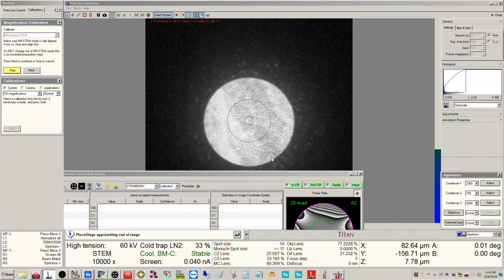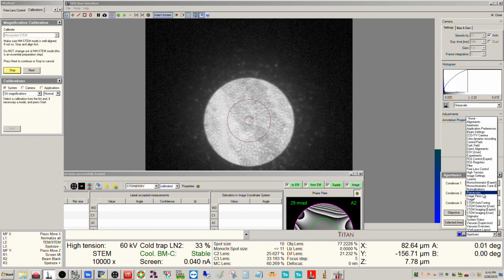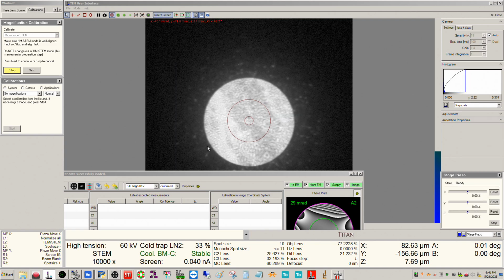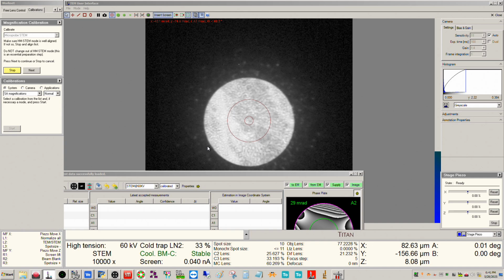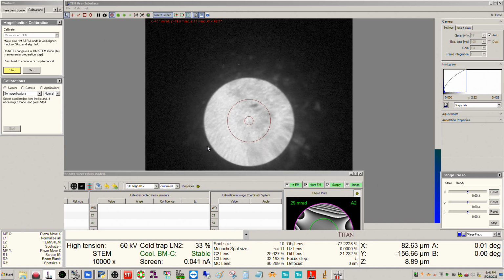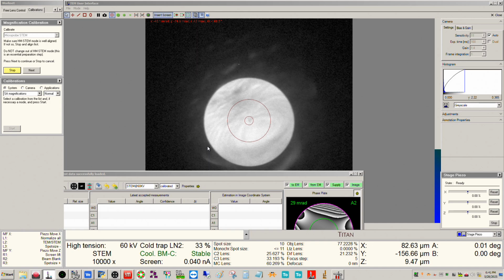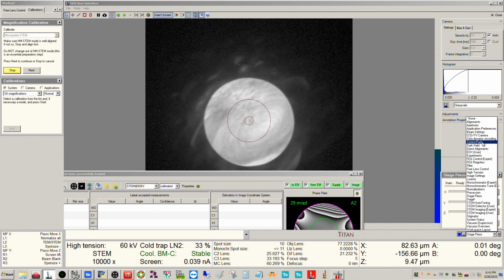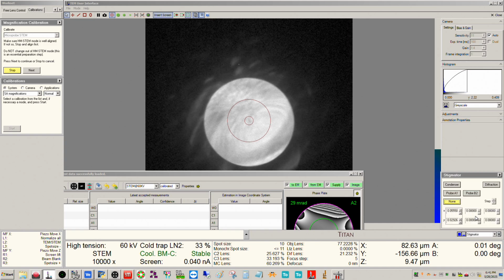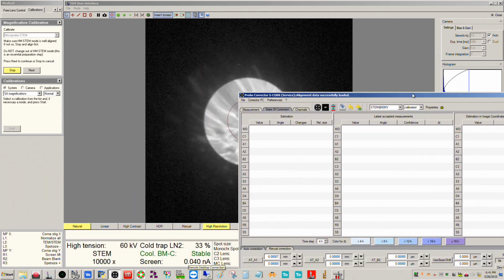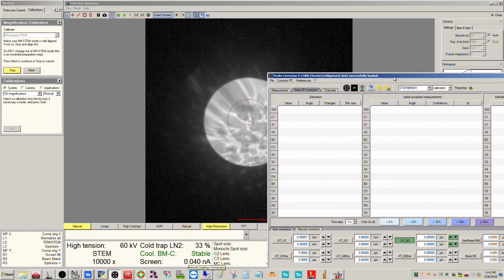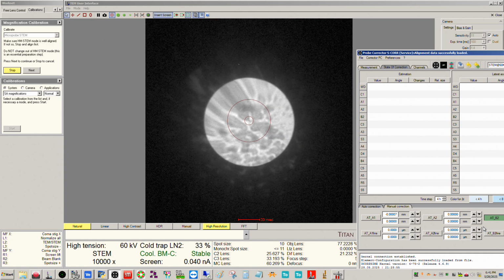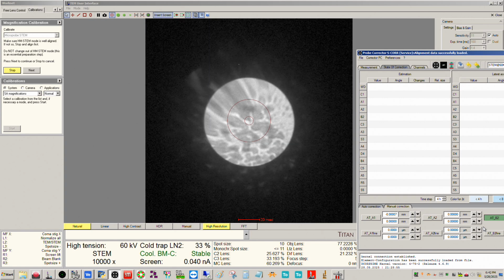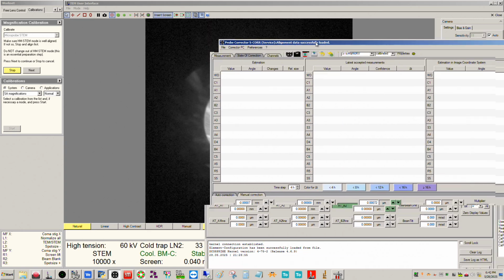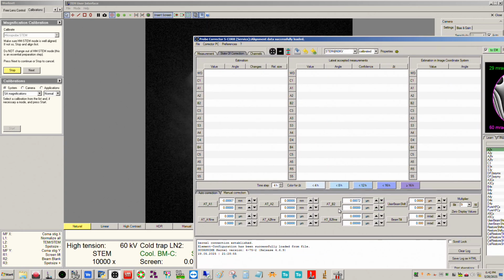Okay, bringing the sample up here. Piezo reset. Okay, so we've got some axial coma. Find the stigmator panel, click probe B2, and we can go ahead and fix this now, A2, B2. Is it doing anything? No, it's on bit multiplier 0. That's why.